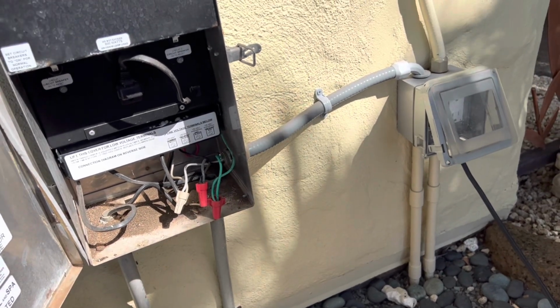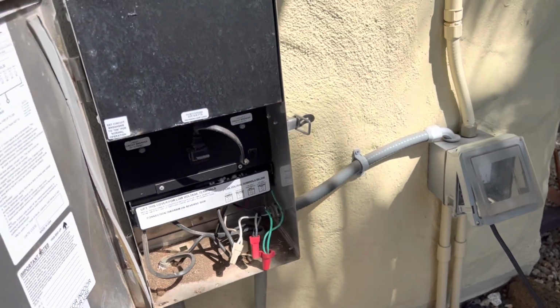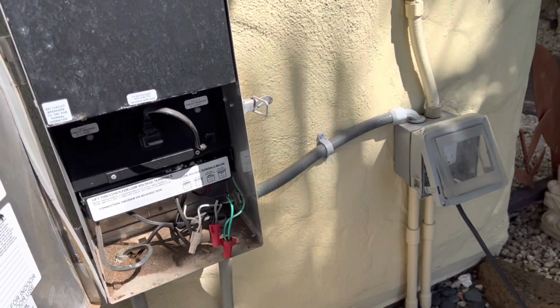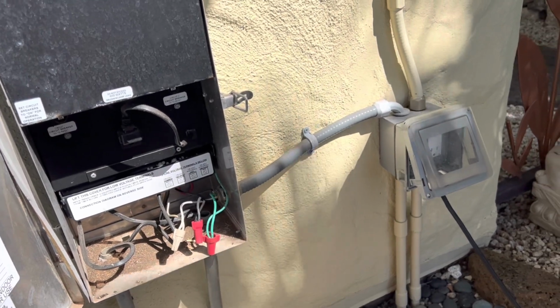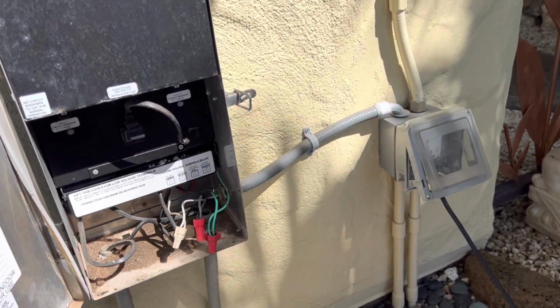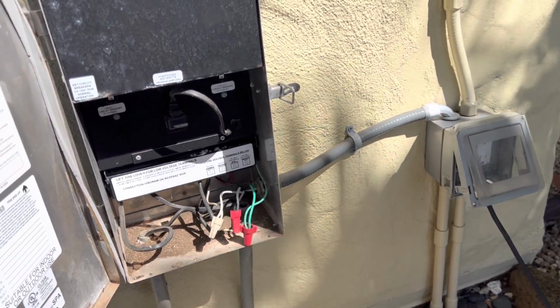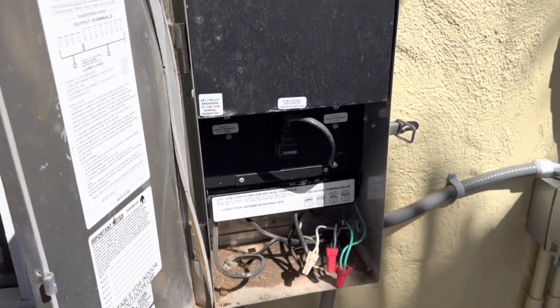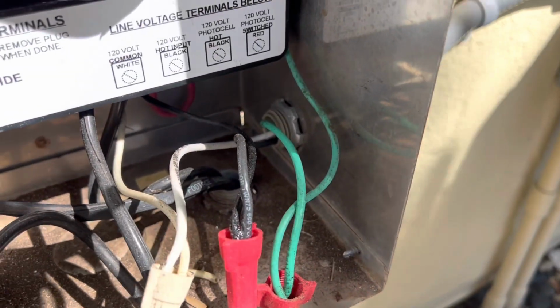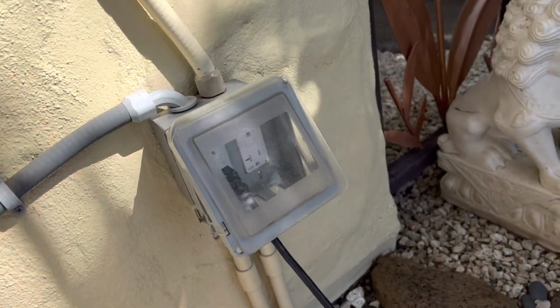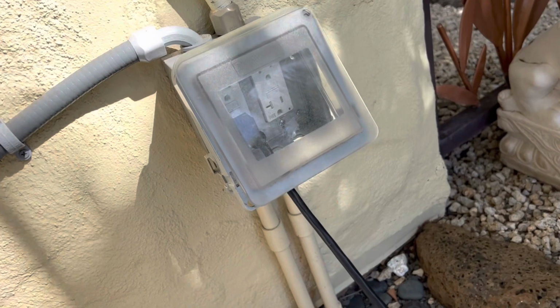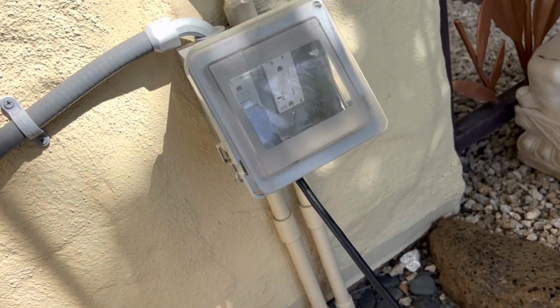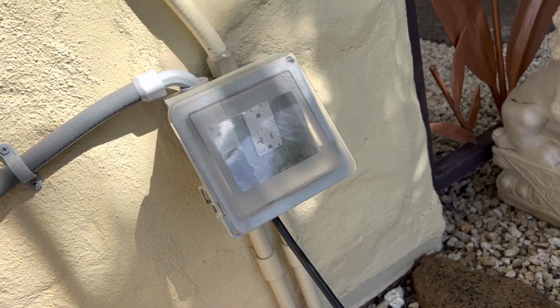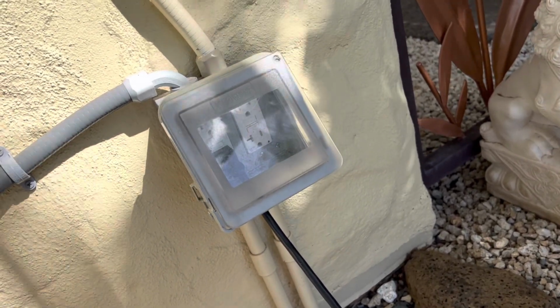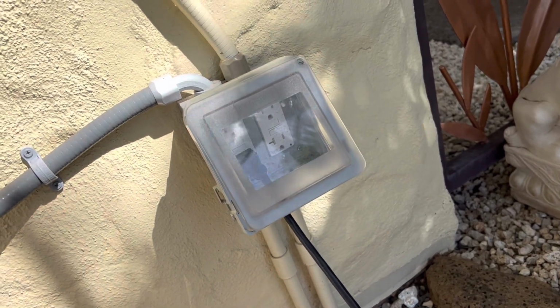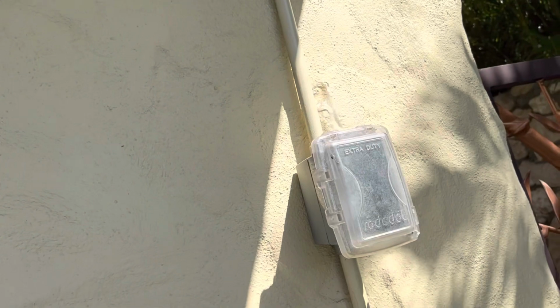Here I am in a situation where there's some low voltage garden landscape lights along with tree lights, and the owner is complaining they don't work. This is the transformer for the low voltage; here's where the power comes in. I think it's hooked up to one of those GFIs—a ground fault interrupter, a type of outlet that protects you from shocking yourself. They're generally required outdoors now by code and around any water indoors. Then there's a switch up there with a timer.